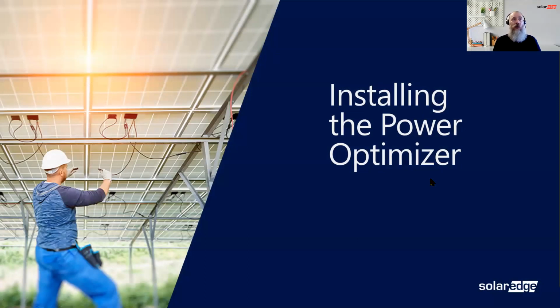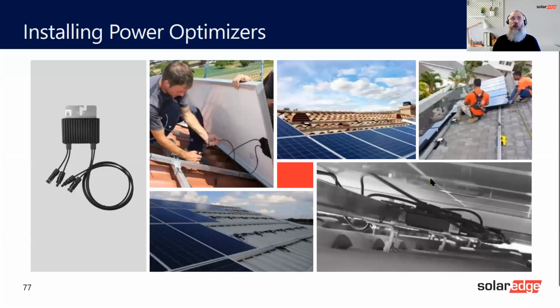So next is looking at installing the power optimizer. As I already said, the benefits of SolarEdge are that you've got the safe DC, the module level, and the output circuit interruption. But the most important one is, don't be confused by saying, oh, I just need this because of shade. Shade is not static. Shade might be a wall or a building that's there now, but that tree is going to grow. The shading is going to change with the cloud. You're going to get animals sitting on it. You're going to get birds nesting on it. It's going to change.